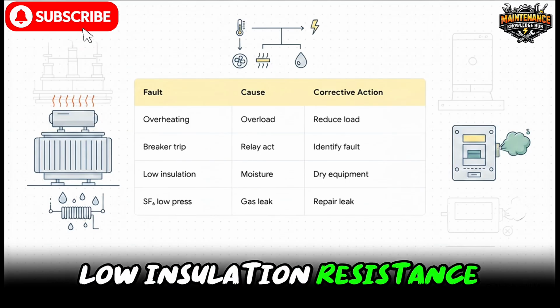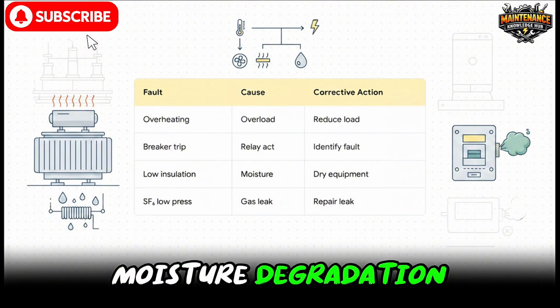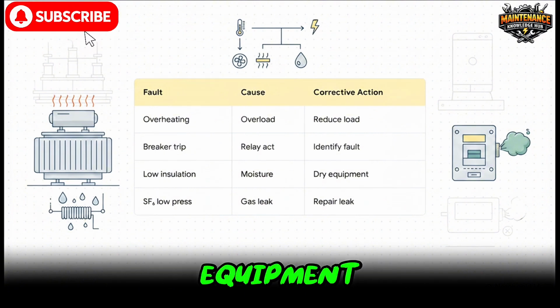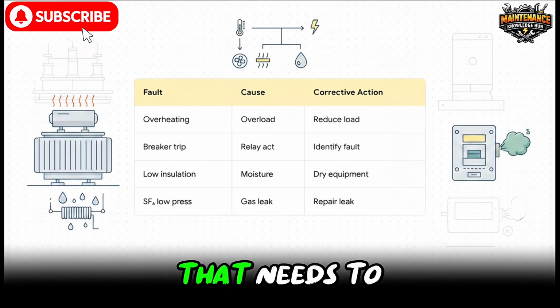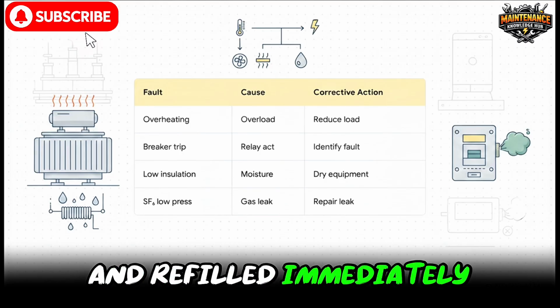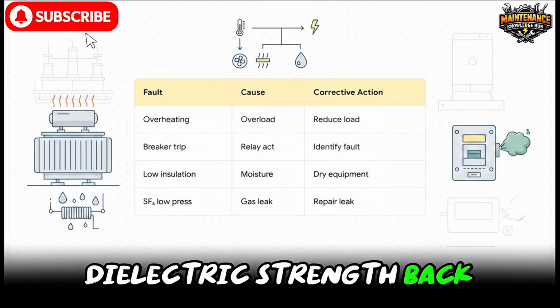Low insulation resistance usually points to moisture degradation, so you've got to dry the equipment. And an SF6 low-pressure alarm, that means you have an active gas leak that needs to be located, sealed, and refilled immediately to get your dielectric strength back.